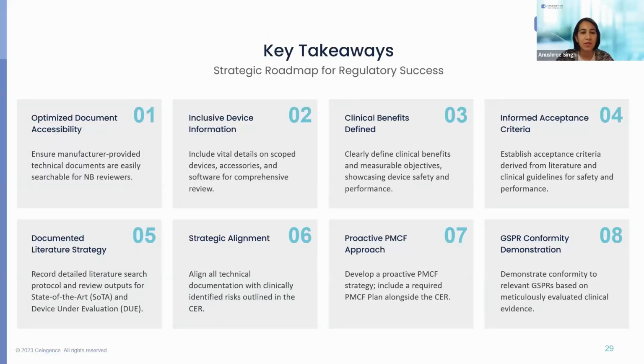Right. So as we are coming towards the end of the session today, we would like to give some key takeaways to bring back to your medical devices. The first one being, make sure that you have the manufacturer-held technical documentation in an easily searchable format for the notified body reviewers. Ensure that you have the detailed device information available, which can also include any accessories that might be used with your medical device, or include information about the software component if applicable. Clearly define the clinical benefits, whether these are direct or indirect, and the associated objectives or endpoints with it, showcasing the device safety and performance.